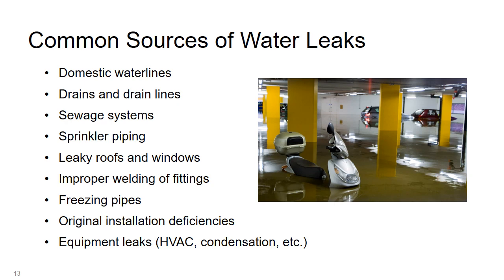Another aspect to keep in mind is that some of these systems have pressurized water. Domestic water supplies can be in the range of 50 to 100 psi from public supply, and sprinkler piping can be as high as 150 psi within a system if there's a booster pump provided. Water at this high of a pressure would be expected to flow out of a pipe at a much higher rate, resulting in more water pooling and spreading within a facility. While these are the most severe, we'll touch on the most common sources of leaks in the next slide.